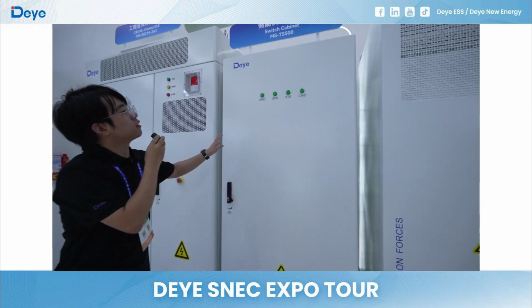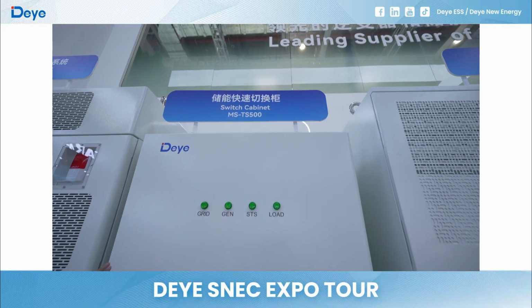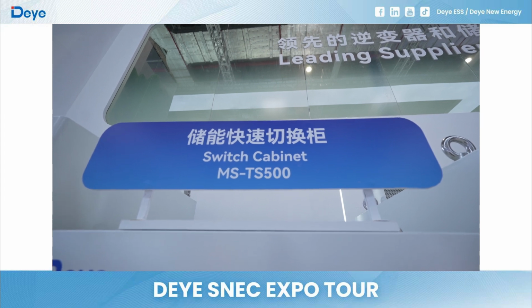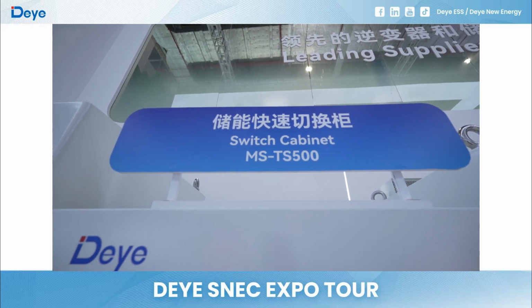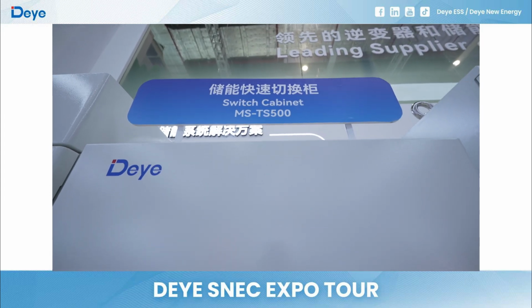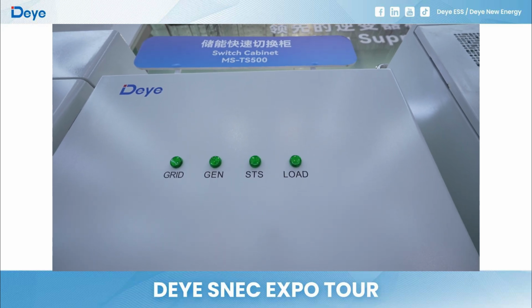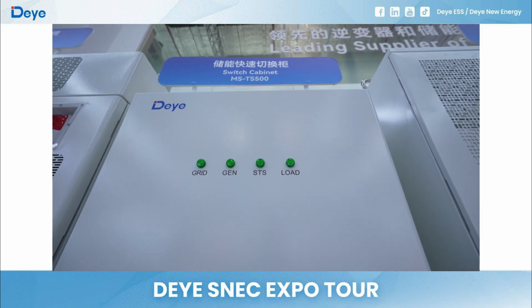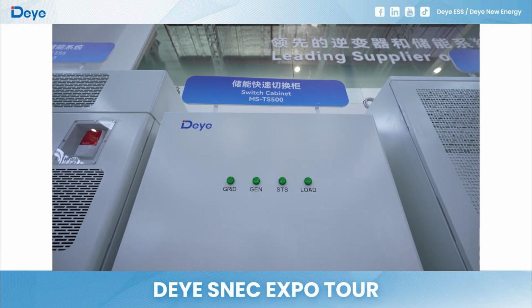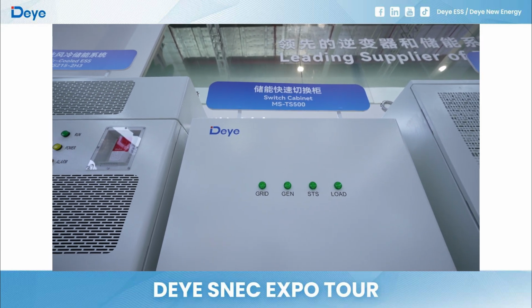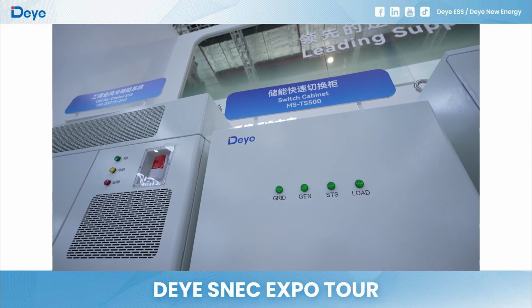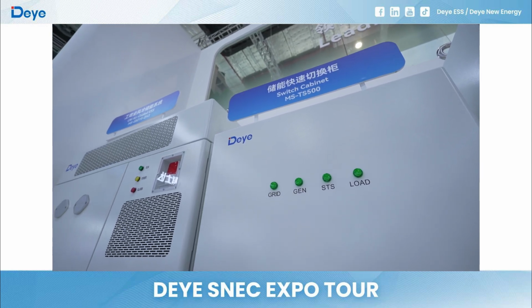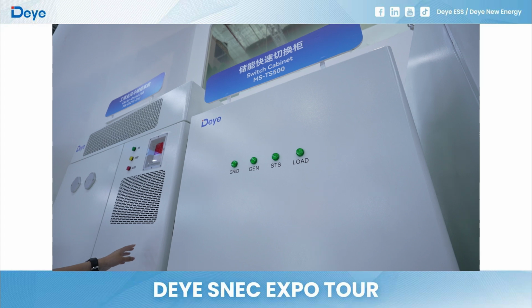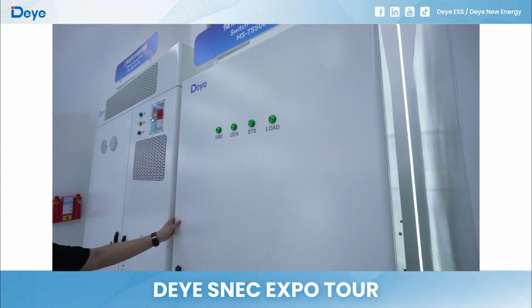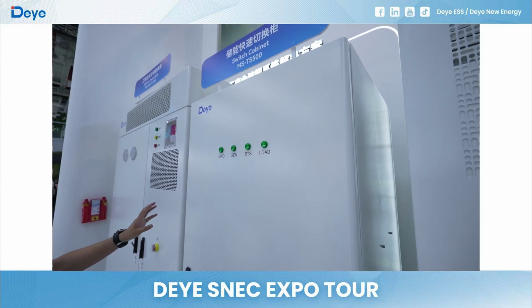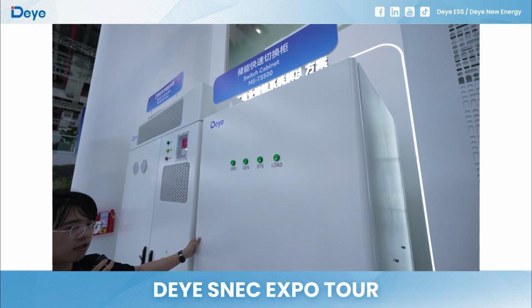Then let's take a look at this one. This is a fast switching cabinet, MS-TS500. Inside this cabinet, it has a 500 kilowatt STS module. This cabinet is usually used with the MS-GS215 to do the fast switching. It can connect 5 MS-G215 cabinets and can do the fast switching in less than 20 milliseconds.